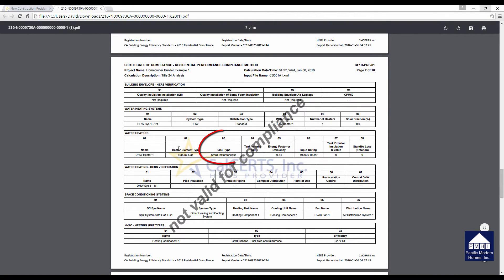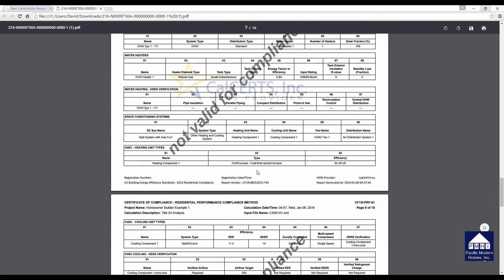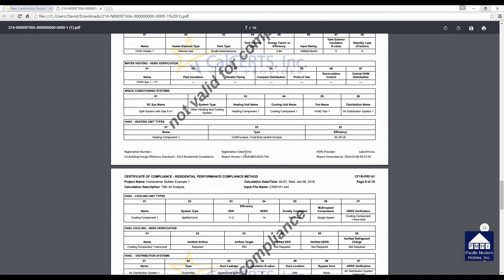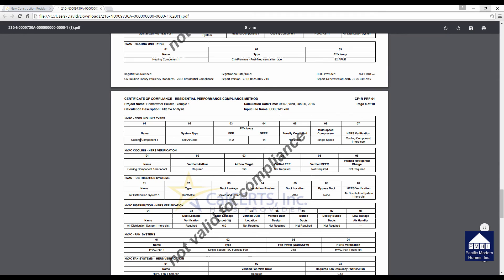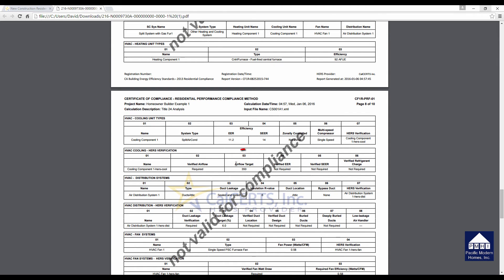You can take a look at the air conditioning information. What was assumed for the air conditioner and the furnace? The furnace has to have an efficiency of 92%. And for the air conditioner, it says the EER has to be 11.2 and the SEER has to be at least 14. If you get involved in some sophisticated heating and air conditioning systems, we can get into zonal controls and multi-speed compressors and take credit for those in the energy calculations. But this is a basic house, so we're not going to be getting involved in those. We are going to be required to do the air flow. It has to flow at least 350 CFM per ton of cooling. One ton of cooling is 12,000 BTUs.